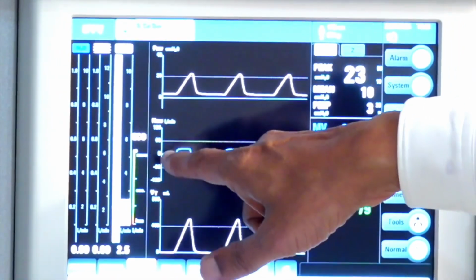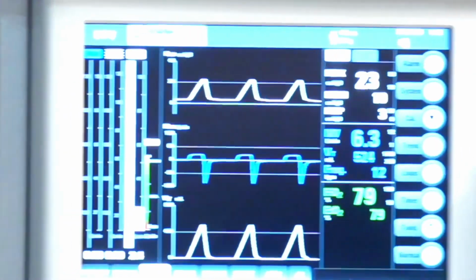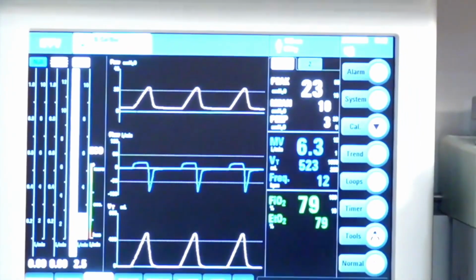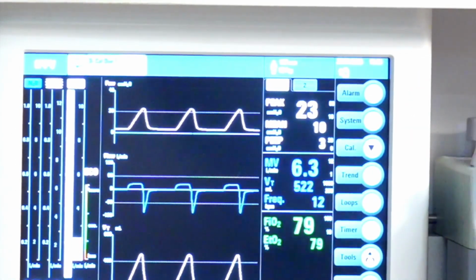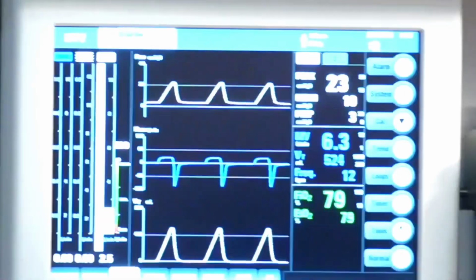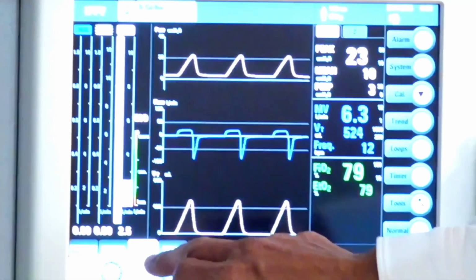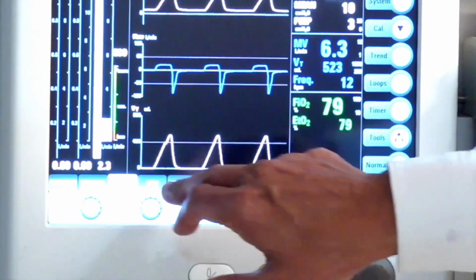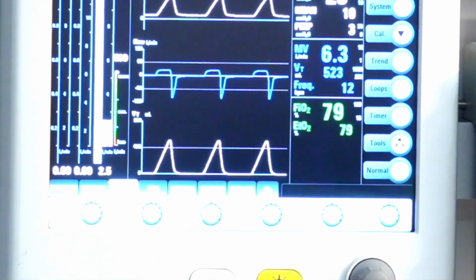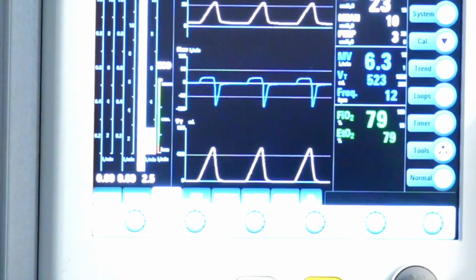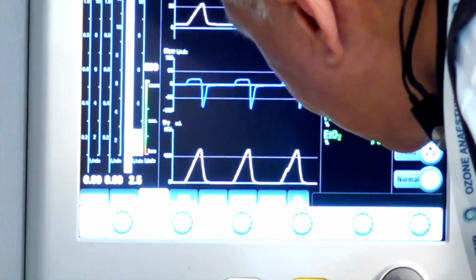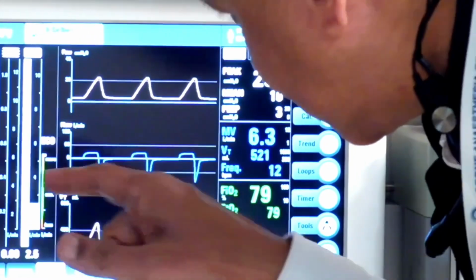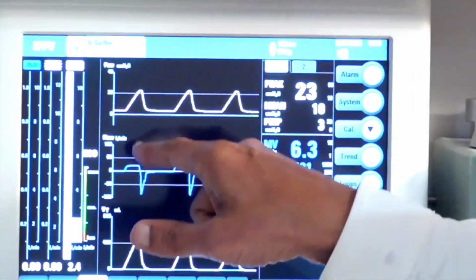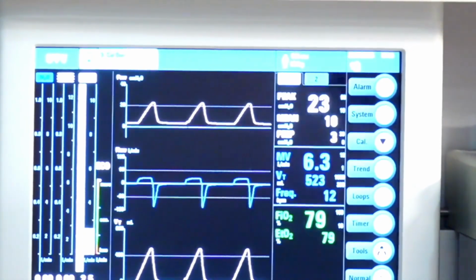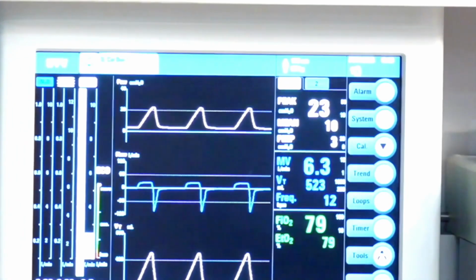What I wanted to show was what Dr. Bandari said. The flow is constant in the volume control mode of ventilation, and the pressure increases. So volume is fixed and the pressure keeps on rising depending upon the patient's lung compliance and the system's resistance. Now, what is pressure controlled ventilation? The pressure is constant and it is achieved by a very high flow initially. So right now, in this flow pattern, the machine's delivered flow rate, can you close up here this part? Okay, so this would be roughly 15-20 liters. That's a peak flow rate.